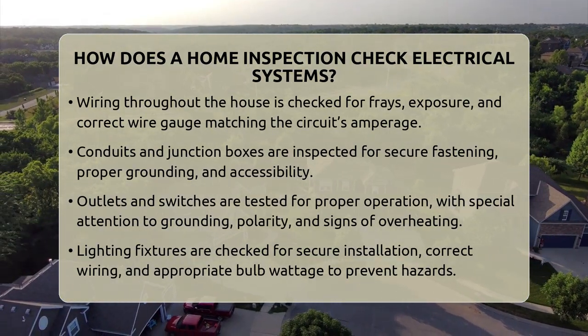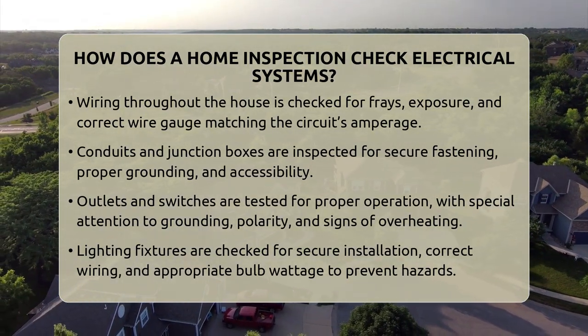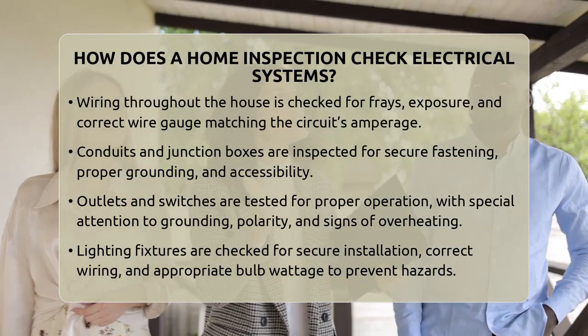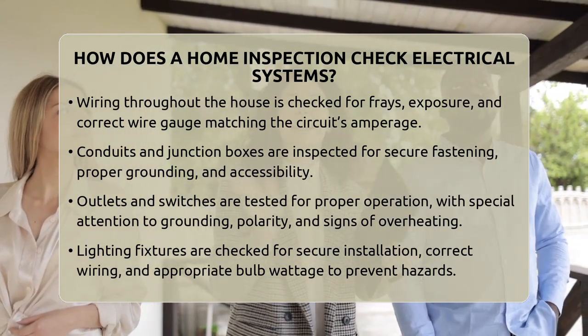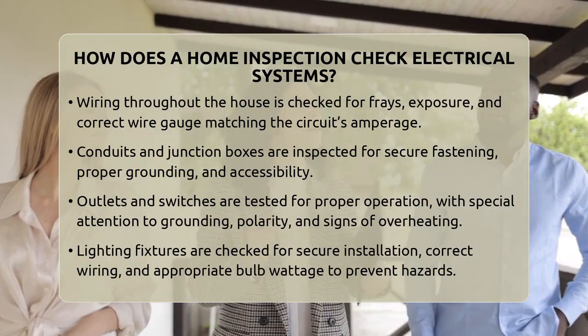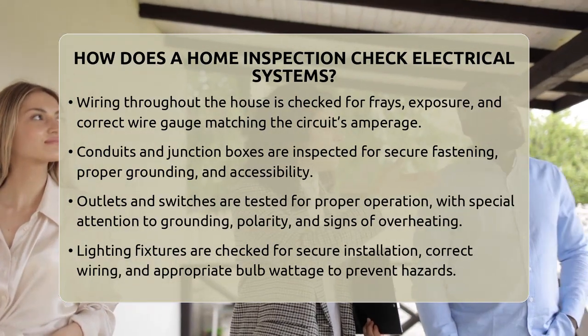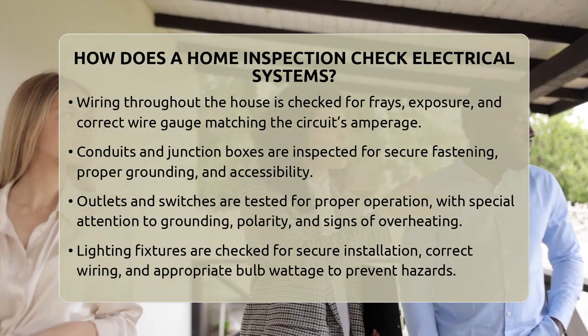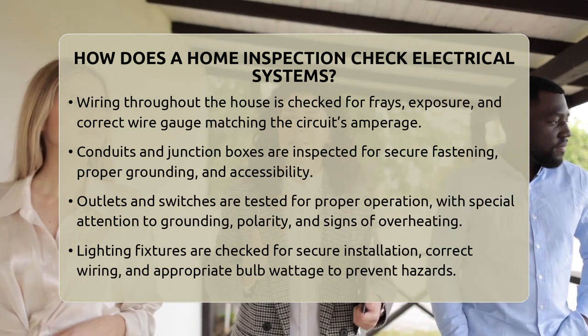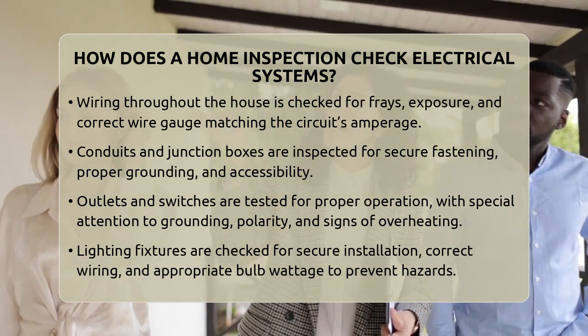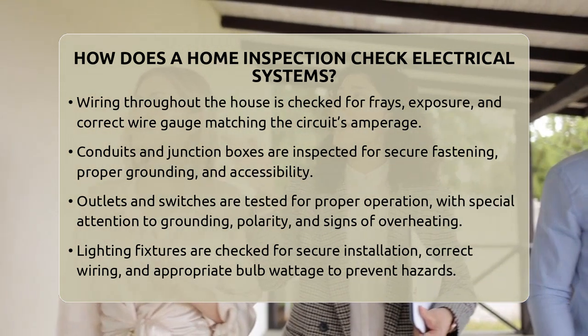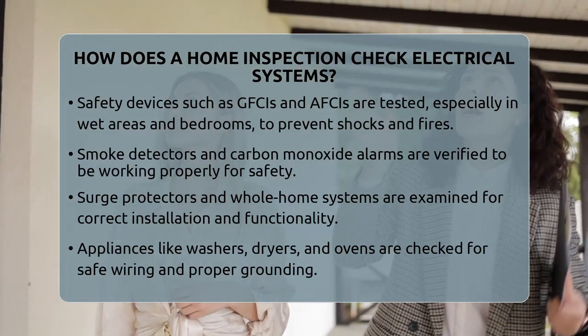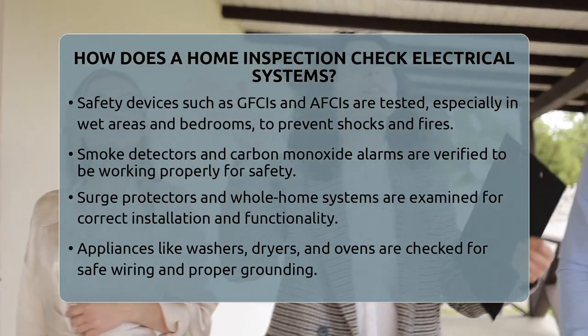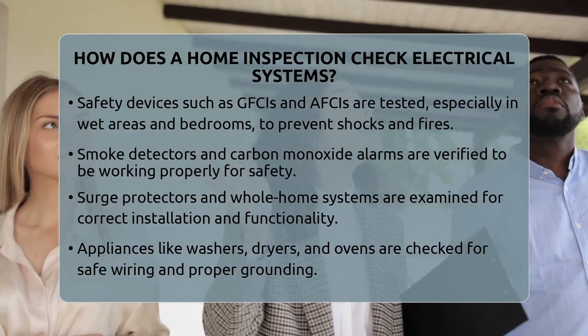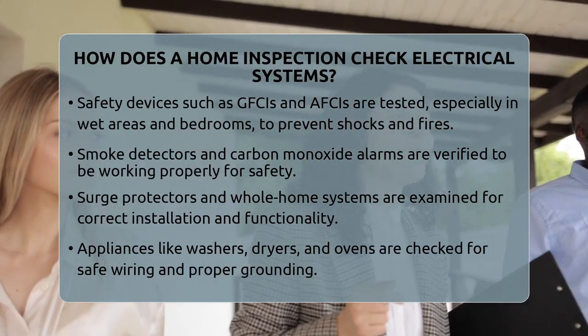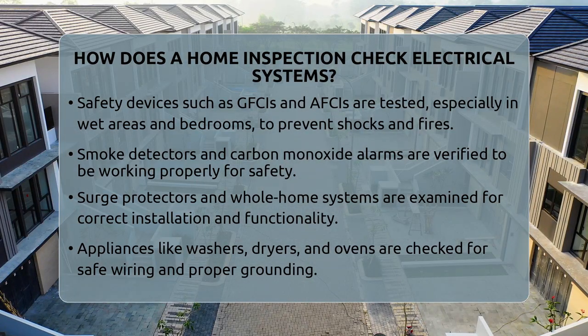Conduits protecting wiring are checked for secure fastening and grounding. Junction boxes are opened to confirm they are covered, accessible, and have proper wire connections. Outlets and switches are tested for proper operation and safety. Grounding is especially checked in older homes. Outlets should not feel warm or hot, as that could mean overloading or loose connections. Reverse polarity or open neutral conditions are serious safety issues that are also checked.